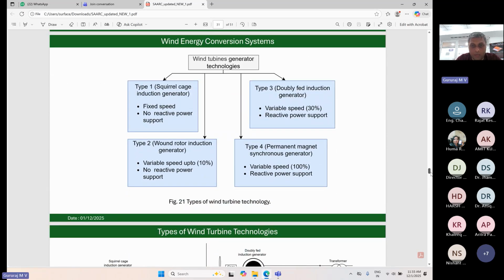So there are various types of generators available. Type 1 is the squirrel cage induction generator. It's more or less fixed speed. There is no reactive power support provided by these induction machines. Rather, the reactive power support has to be rendered from the grid, or if you have some capacitor banks or STATCOMs, you can manage it by yourself. And type 2 is called wound rotor, where we use the wound rotor induction generator. Some variation is possible with respect to the wind speed harnessed, up to 10%. However, not much reactive power support can be expected from these generators.